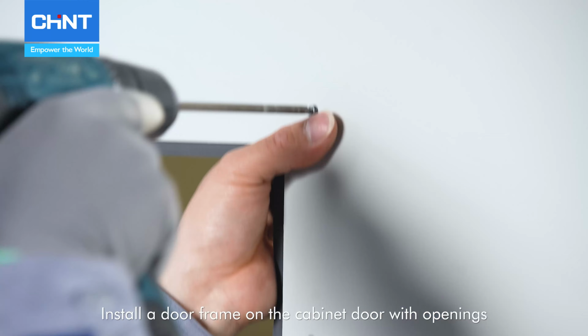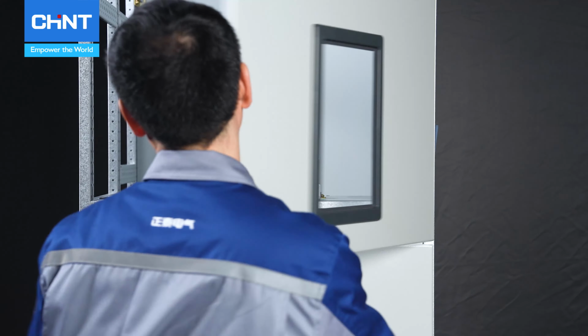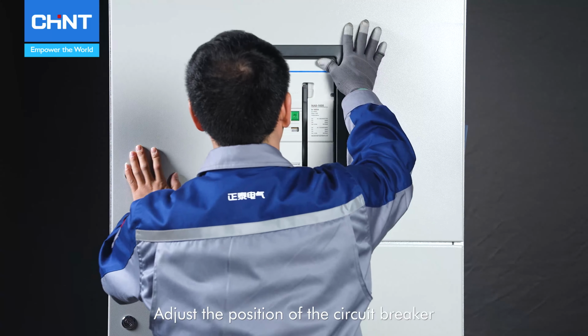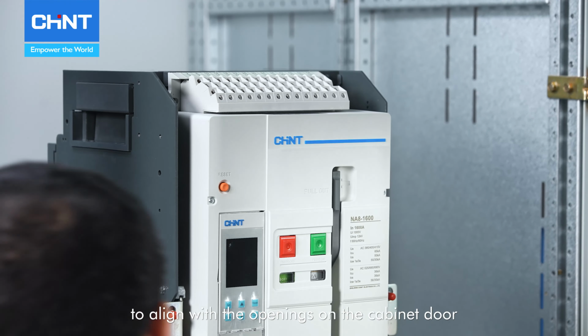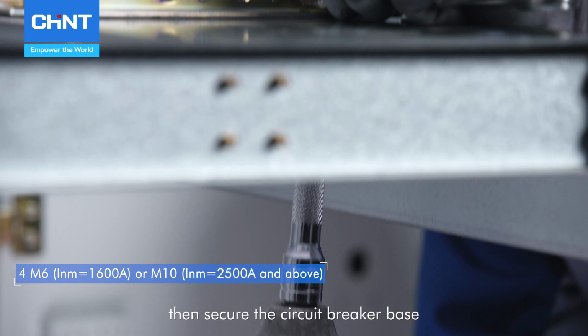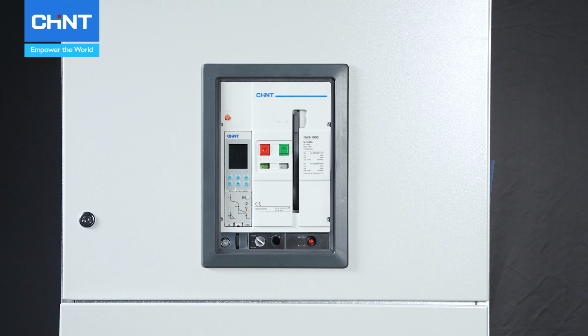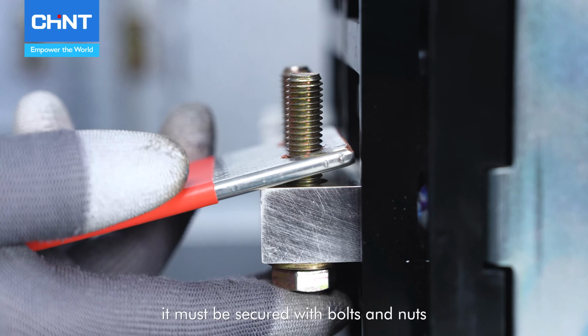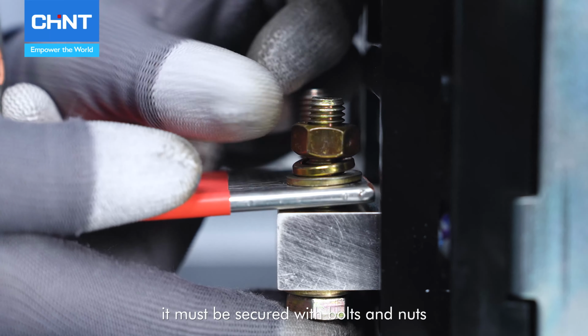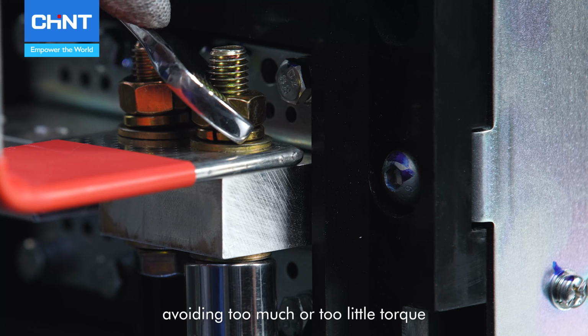Install a door frame on the cabinet door with openings. Adjust the position of the circuit breaker to align with the openings on the cabinet door, then secure the circuit breaker base. When installing the bus bar, it must be secured with bolts and nuts, avoiding too much or too little torque.